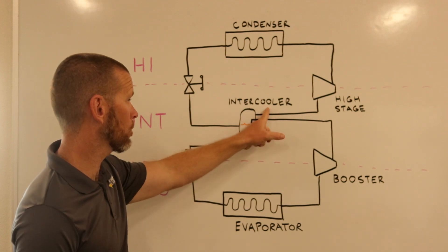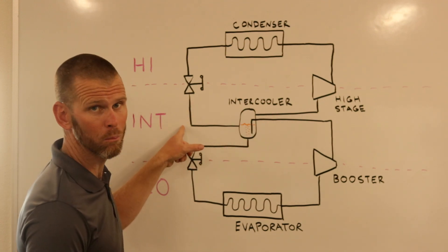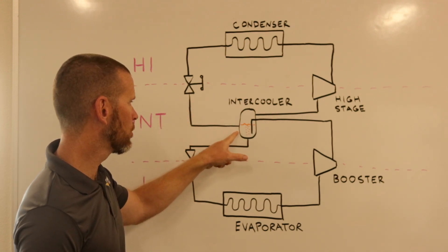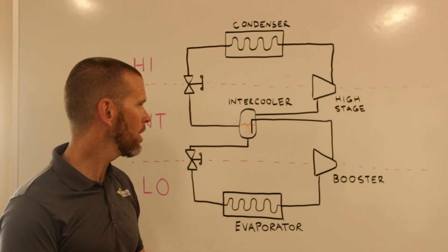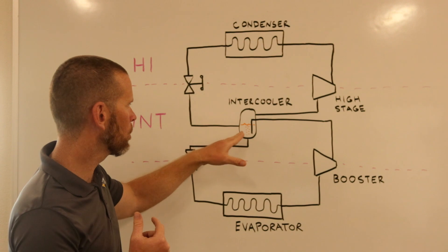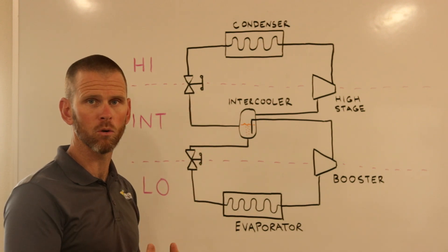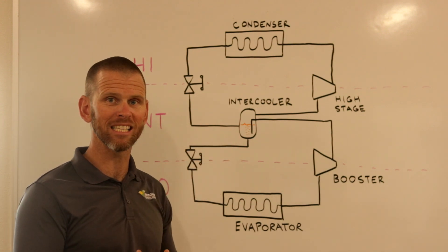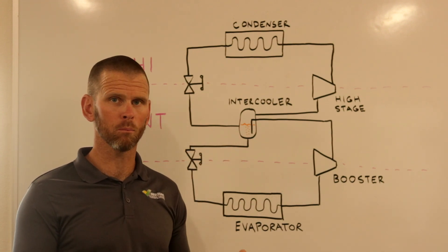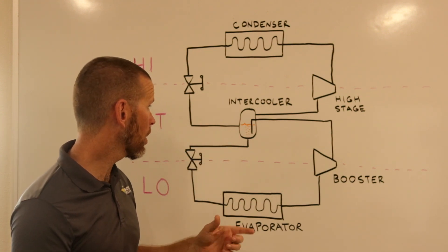We now have a lower-pressure liquid that enters our new component that's part of this two-stage system, and that is called an intercooler. This lower-pressure liquid enters the intercooler, and there would be some sort of solenoid valve that is interlocked with some sort of flow control or level control so that we maintain a level inside that intercooler of this lower-pressure liquid.